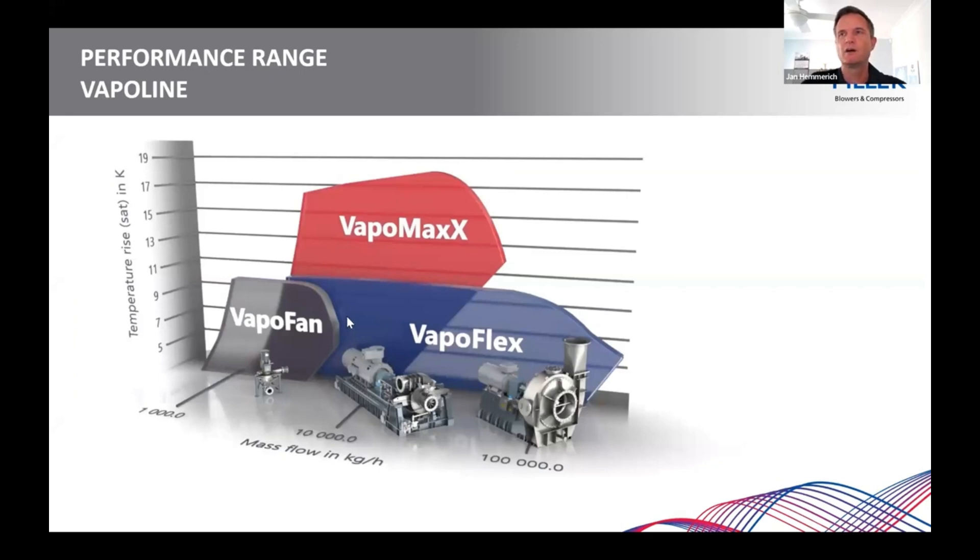Here I want to show you the performance range we are able to cover with our VapoLine. On the left-hand side, the purple area shows what the Vapor Fan is capable of — these conditions are in ambient at 100°C saturated steam. Note that the axis is logarithmic, not linear. The VapoFan itself is for very low flows up to 5 tons per hour in ambient conditions. The VapoFlex, as the name says, is very flexible and can achieve a mass flow up to 250 tons per hour, still with very high delta-T's.